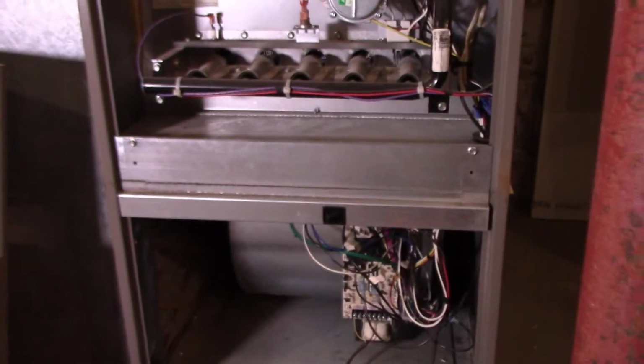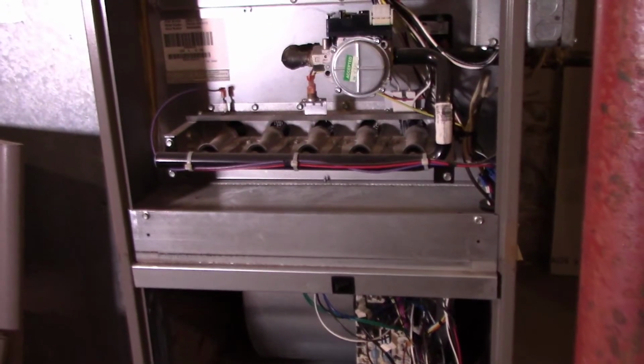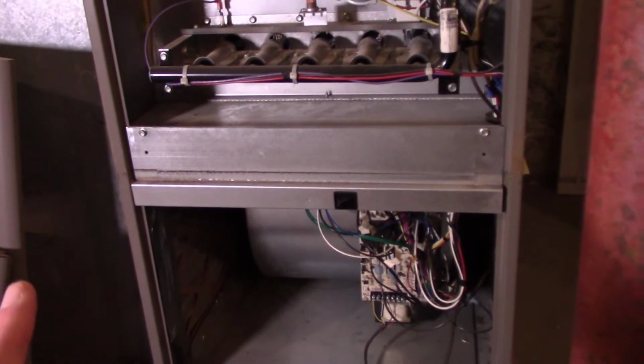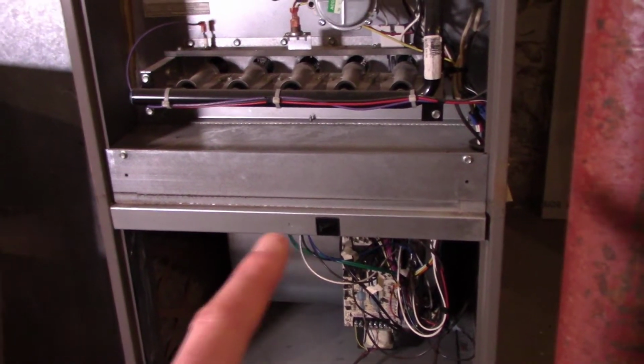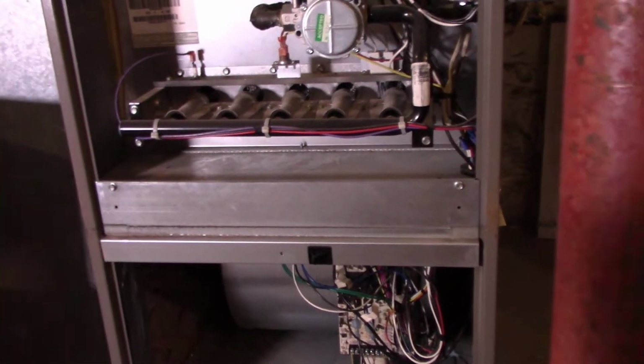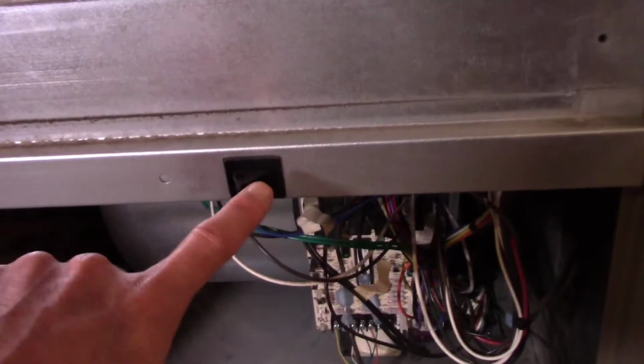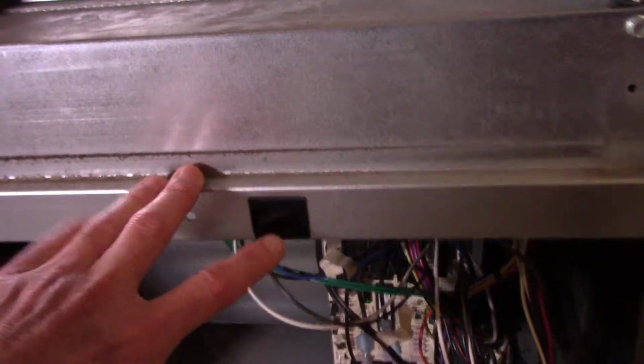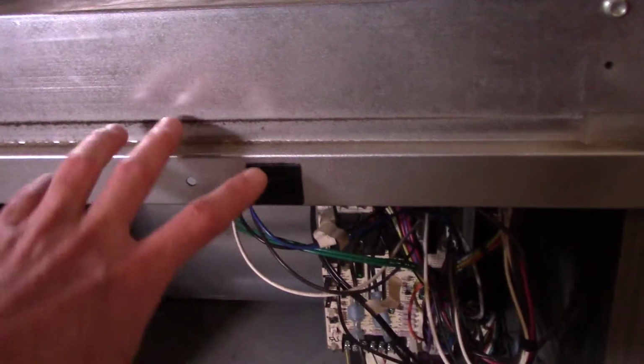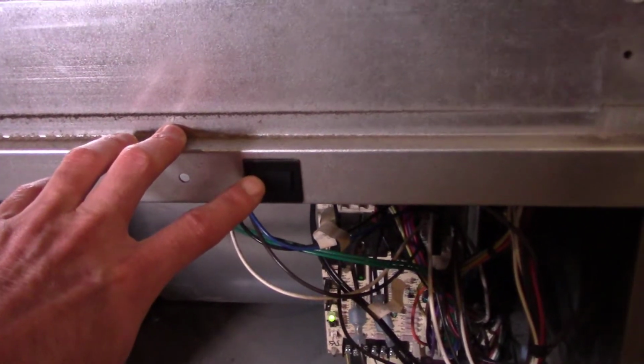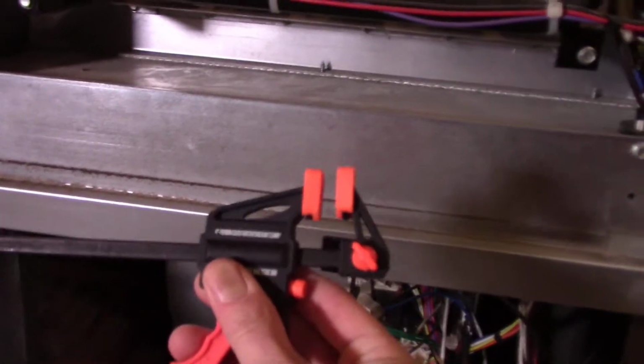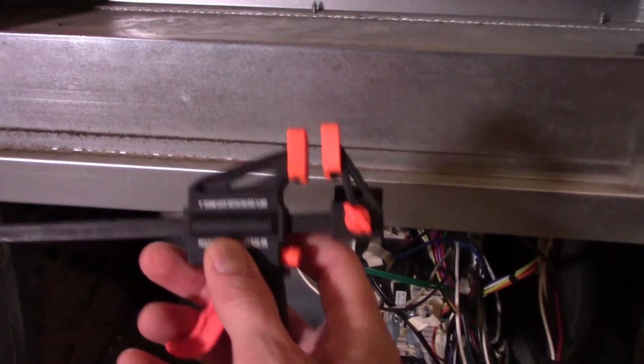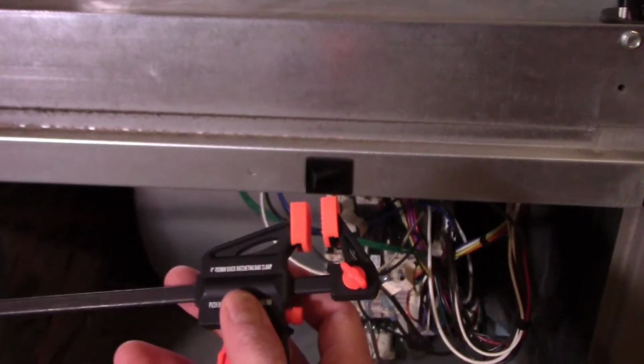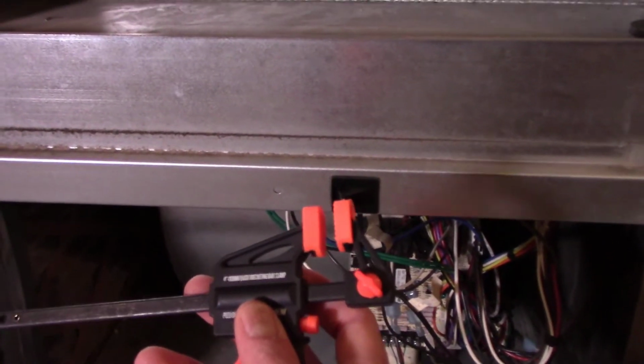But what's really common, and a mistake homeowners make, is that when you open the doors on the furnace, there's almost always a door switch that is also cutting the power off as a safety mechanism, so if you have the doors off, the furnace won't run. And as you can see, that's right here. So when you're troubleshooting and you want to see the furnace run without the doors open, you could tape the switch down, or what I like to do is I always keep one of these little clamps in my tool bag, and I can clamp that switch closed so that we can do further investigation on the furnace while the doors are open.